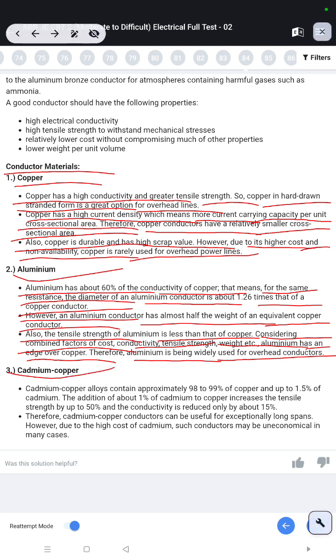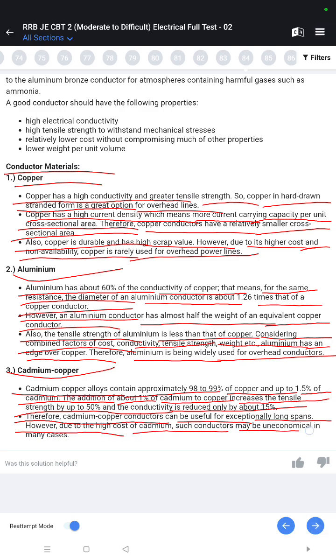Cadmium copper. Cadmium copper alloy contains approximately 98 to 99% of copper and up to 1.5% of cadmium. The addition of about 1% of cadmium to copper increases the tensile strength by up to 50% and the conductivity is reduced only by about 15%. Therefore, cadmium copper conductors can be useful for exceptionally long spans. However, due to the high cost of cadmium, such conductors may be uneconomical in many cases.